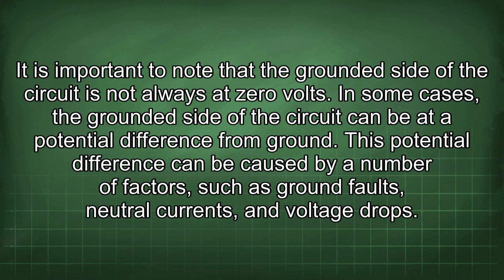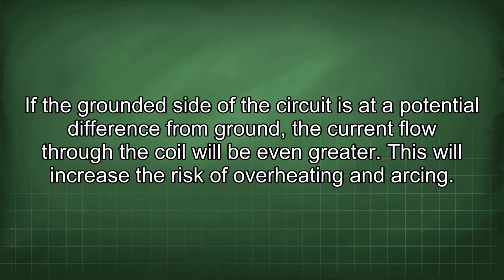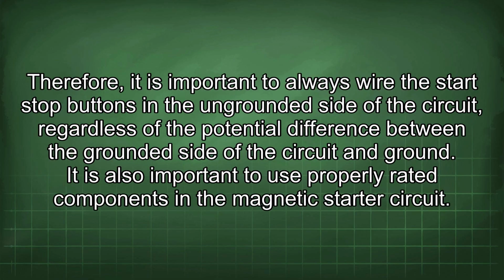It is important to note that the grounded side of the circuit is not always at 0 volts. In some cases, the grounded side of the circuit can be at a potential difference from ground. This potential difference can be caused by a number of factors such as ground faults, neutral currents, and voltage drops. If the grounded side of the circuit is at a potential difference from ground, the current flow through the coil will be even greater. This will increase the risk of overheating and arcing. Therefore, it is important to always wire the start-stop buttons in the ungrounded side of the circuit regardless of the potential difference between the grounded side of the circuit and ground.